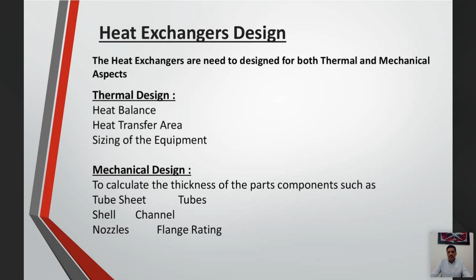Once we finish the thermal design, we will look into the mechanical design. What is mechanical design? Mechanical design is to check the integrity of the equipment, whether the equipment will work under the pressure or temperature or not, whether we selected the right material or not, or whether we have a proper thickness of the components. In order to check the mechanical design, you will check the tube sheet, tube, shell, channel, nozzle, and flange rating components, which are the pressure parts components in the heat exchanger design.